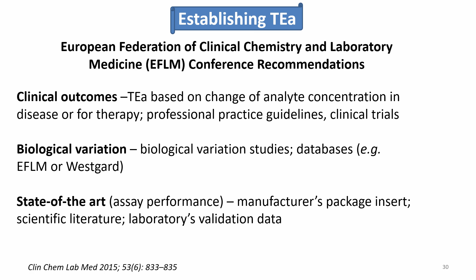You can also establish the allowable total error on biological variation data. Biological variation is the variation of an analyte when a patient's health status is stable. That's the natural variation of an analyte, and it's different for different analytes. You can find this information in databases like the EFLM database and the Westgard database, and I will show you an example of this, because this is actually what CLIA used to establish the new PT acceptability criteria. You can also use state-of-the-art assay performance. This data can be obtained from the manufacturer's package insert, the scientific literature, and the lab's own validation data. Please look forward to the EP46 document coming out. It's going to discuss each of these approaches thoroughly.